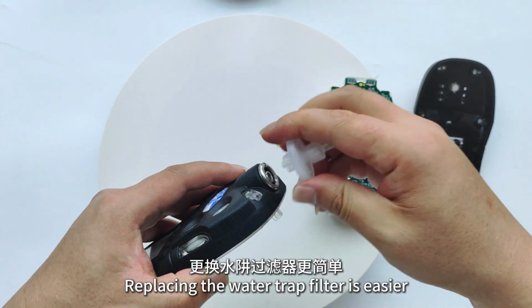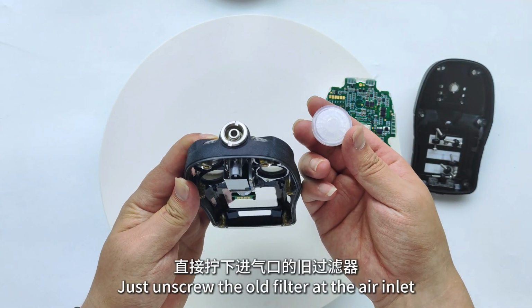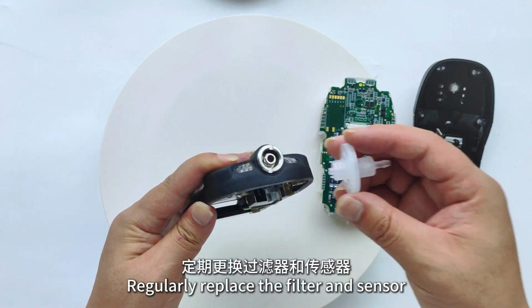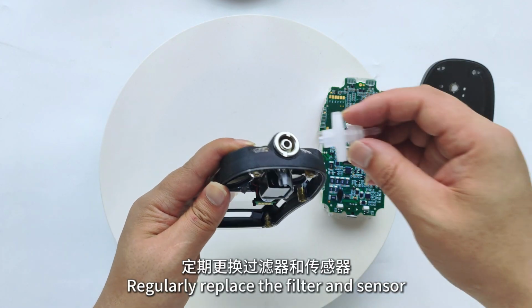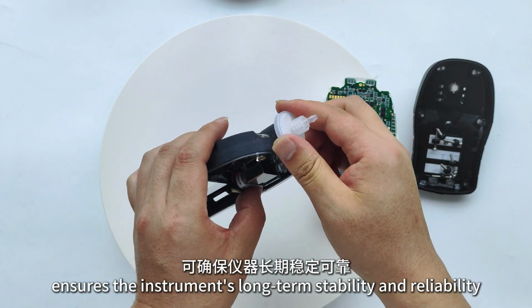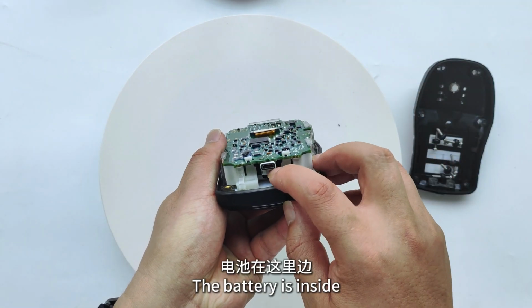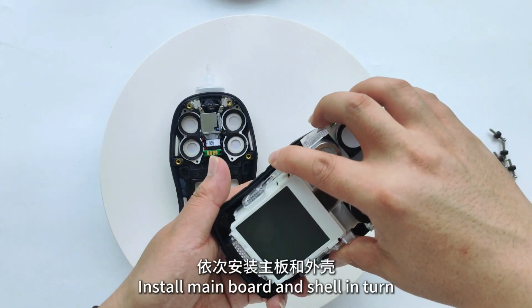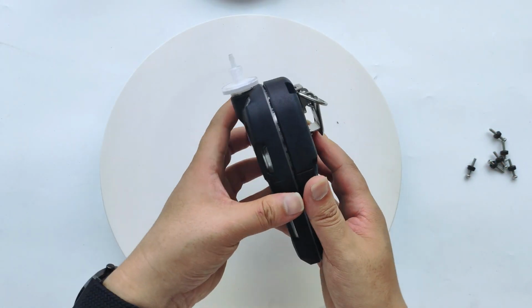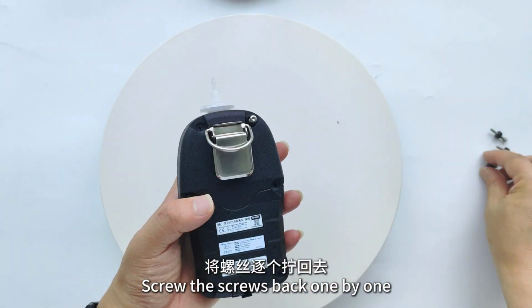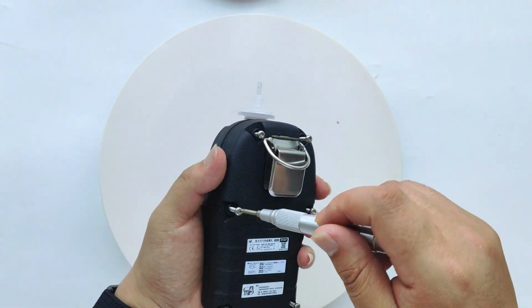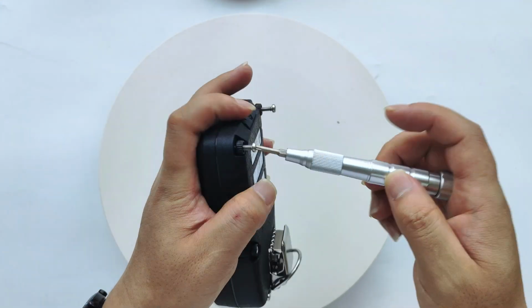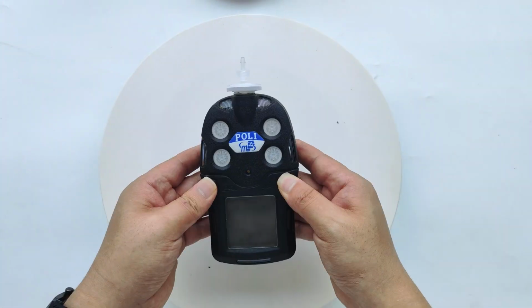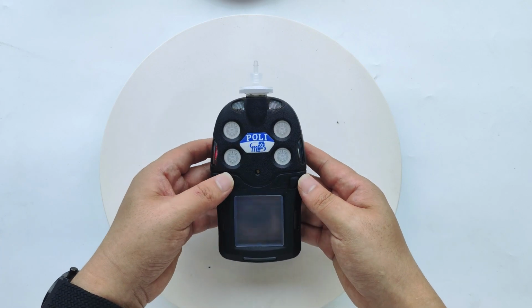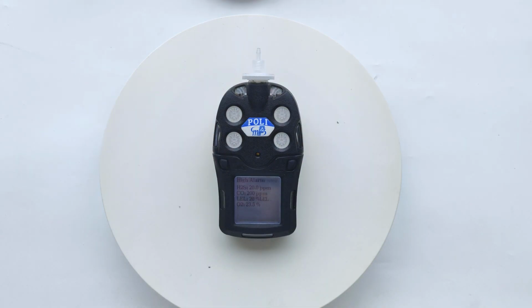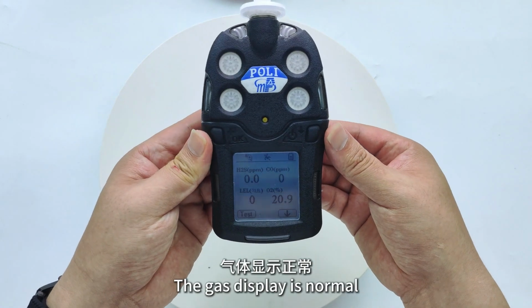Replacing the water trap filter is easier. Just unscrew the old filter at the air inlet and replace it with a new one. Regularly replace the filter and sensor. This ensures the instrument's long-term stability and reliability. The battery is inside. Install the mainboard and shell in turn. Screw the screws back one by one. The sensor replacement is done. Let's reboot. The gas display is normal.